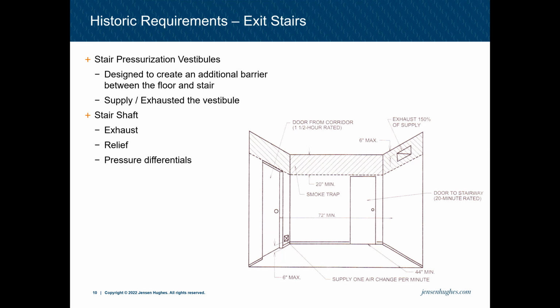There were relief vents as part of requirements for these stair pressurization shafts. We'll hear the term VFD quite a bit, a variable frequency drive. Before those were created, we basically just had a fan blowing a specific amount of air. The issue is that if you're blowing in a bunch of air and the pressure is really high, we want people to get into the stair. So if we have too high of a pressure, we can't necessarily push in the door. And these relief vents will bleed off pressure if it got too high, so we could still allow people into the shaft.